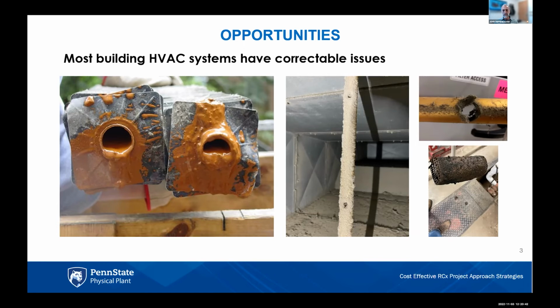Another example of good intentions is precise measuring of outside air so that you meet the ventilation requirements, but you don't supply excess outside air CFM. But what we found is that thermal dispersion type airflow measuring stations are very susceptible to dirt. In the outdoor air application and the return air application, we were getting errors of 5 to 10-fold, and it was on the bad side. It was under-reporting. The control system would say you were getting 1,000 CFM, and we were actually getting 5,000 to 10,000 CFM. So big energy impact there.